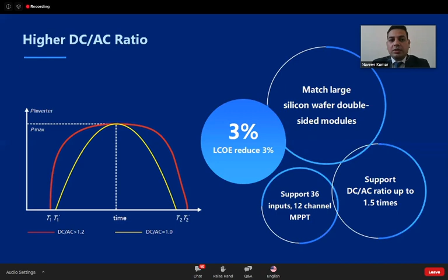Moving on to friendly grid connection, I have divided this part into four sections. The first: as I mentioned, in today's scenario we are using a DC-AC ratio of more than 1.5, where at peak time we lose some power which is more than the capacity of the inverter. This is called clipping. So how can we save this clipped energy by storing it in a battery? Our inverter has a DC-DC coupling feature by which we can store this clipped energy in the battery, which can be used later for grid smoothing and grid support features.